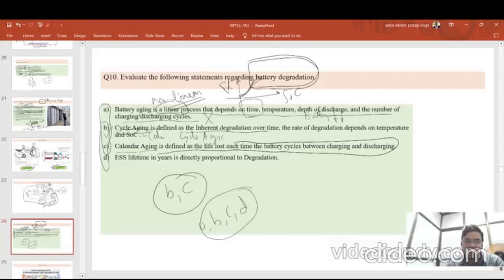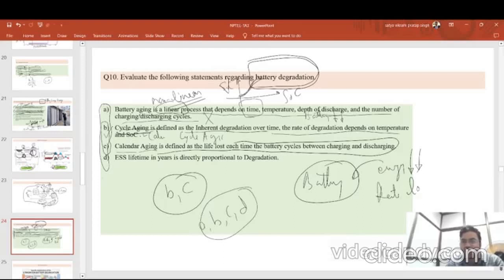In statement B, it is actually calendar aging. Calendar aging means if you keep the battery unused for several years, its energy will drop down and degrade, but at a low rate compared to cycle aging - still, it will degrade. Coming to option D, that is also false, because the energy storage system lifetime is not directly proportional to degradation, it is inversely proportional. This means all statements are false: if degradation increases, the energy storage lifetime will decrease, and if degradation is low, the lifetime of the energy storage system will be high.